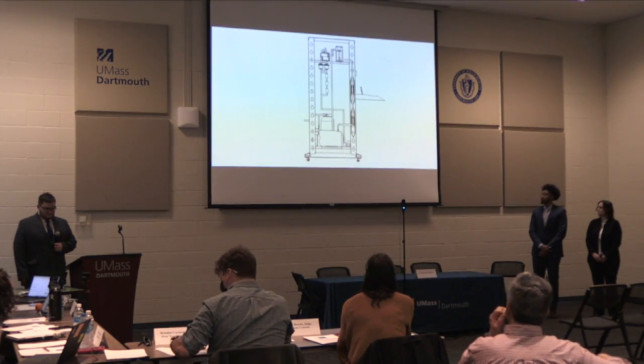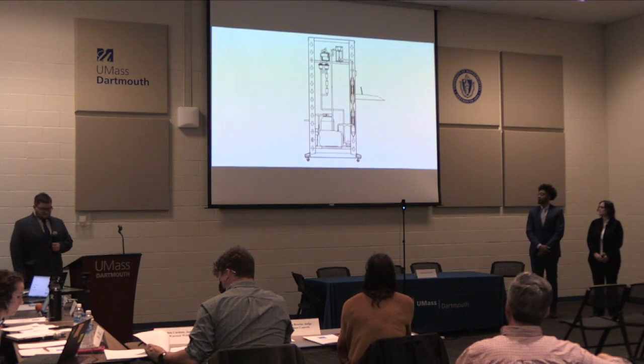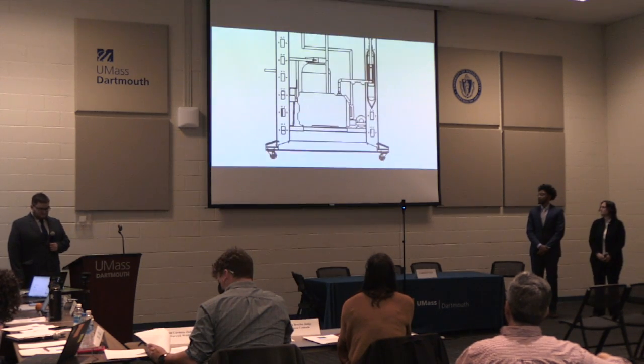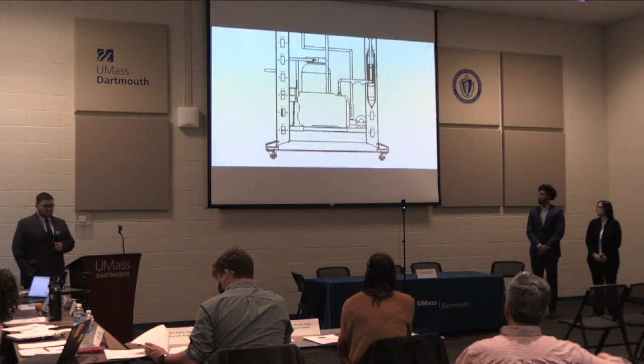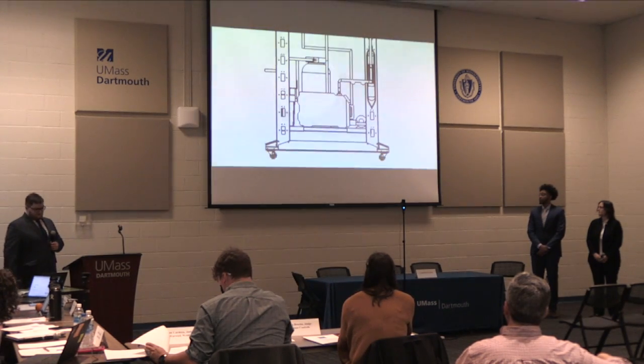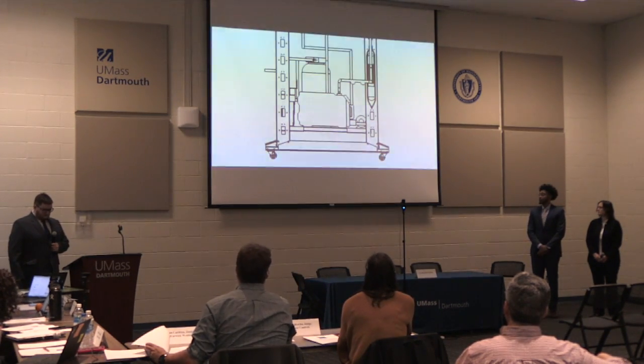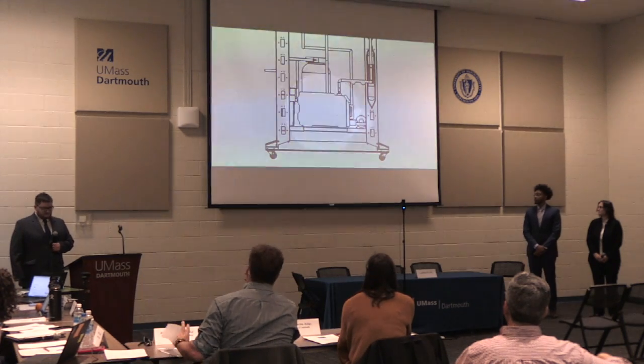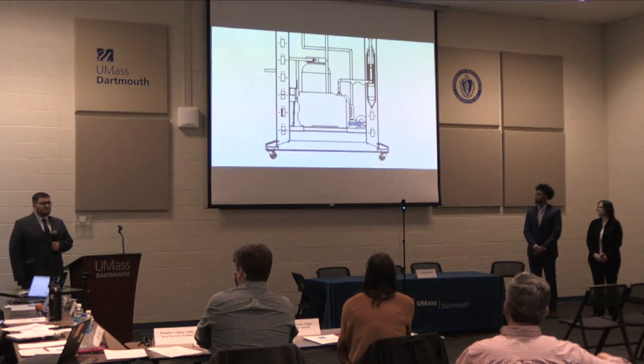Our prototype solution is a portable closed-loop system that filters water before it's chambered through our LISST-Tau sensors. Tap water is supplied to the system's inlet, where it's run from the primary filter and a deionizer. The pre-filtered water is stored in the reservoir tank and is then fed into a pump which transports water upwards to be purified.